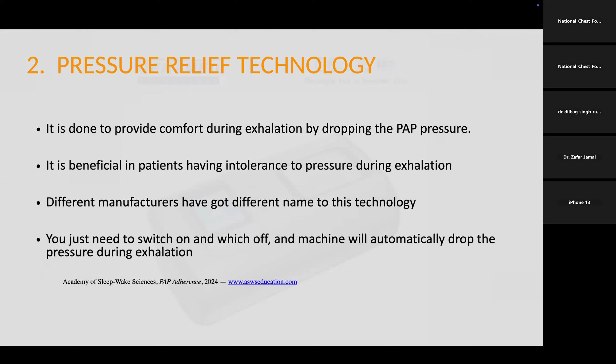So how to adjust the setting? If you are using a ResMed machine, go to the comfort setting, and here it is called expiratory pressure relief, and you just need to turn on the setting. And there are levels 1, 2, and 3; mostly in our patients we set the level between 1 and 2, because at expiratory level 3 the pressure drop can be up to 3 centimeters during exhalation. And in those patients who have a high AHI, and those who have some part of OHS, in these patients it can cause pharyngeal collapse, which can lead to residual AHI.